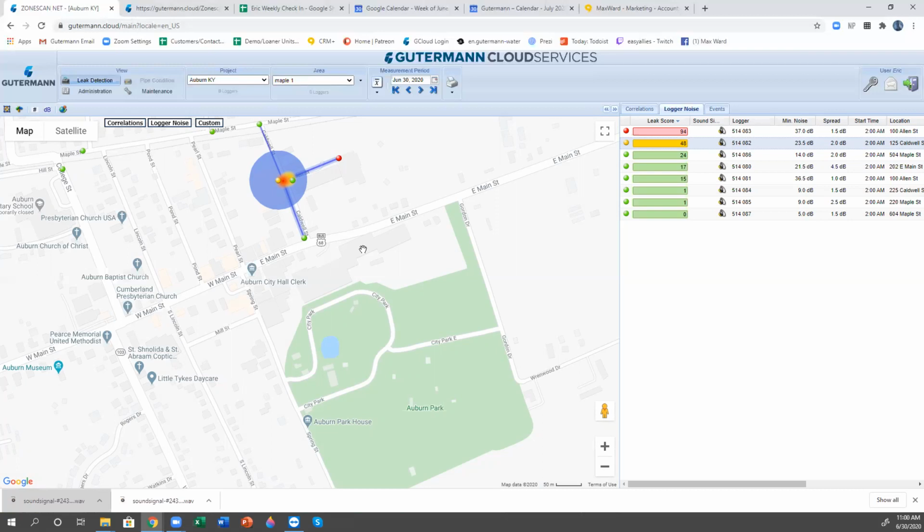It can say there's two things going on in this area. There's this low frequency brook noise, and then there's this high leak noise. So it can differentiate that. You might get a small percentage correlation on a creek. If the water's running directly over the pipe, or if there's a little bit of earth between the two, you probably won't get anything from the creek.